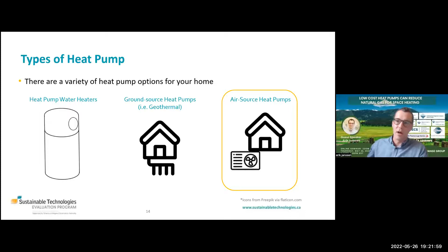This is a quick schematic of what an air source heat pump looks like. It's essentially an air conditioner that can operate in two directions. It looks the same as an air conditioner and has many of the same refrigeration components. It's typically a split refrigerant circuit, with something outdoors that looks like an air conditioner and something indoors, which could be a ductless fan coil, an air handler, or even integrated into a furnace. Refrigerant piping connects the system together, and components like the compressor and expansion device should be familiar to HVAC folks as standard air conditioner parts.